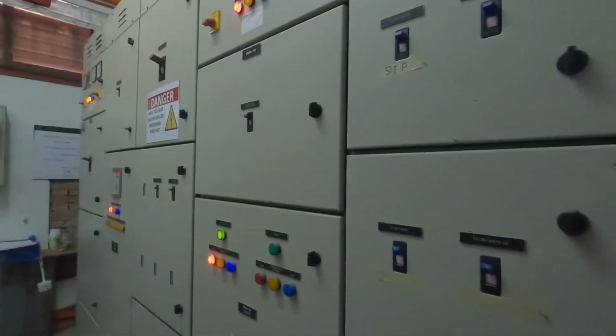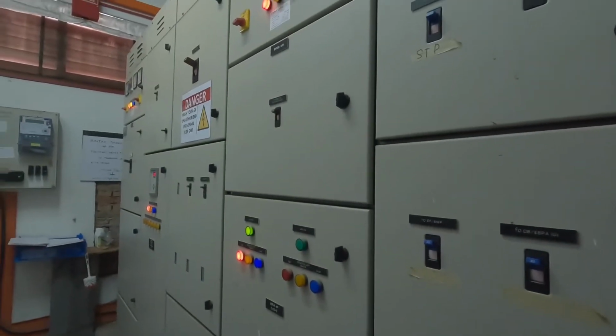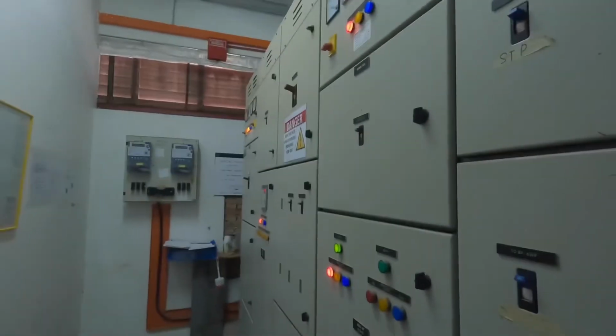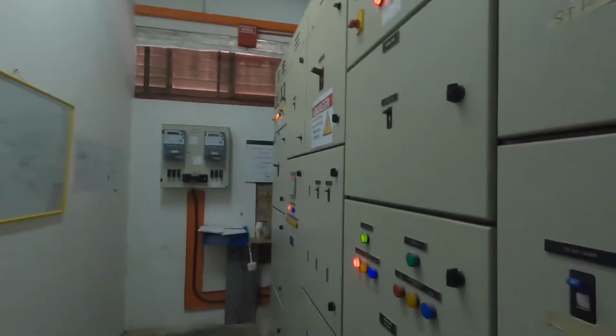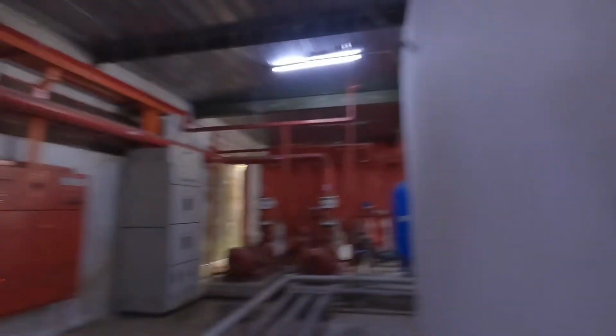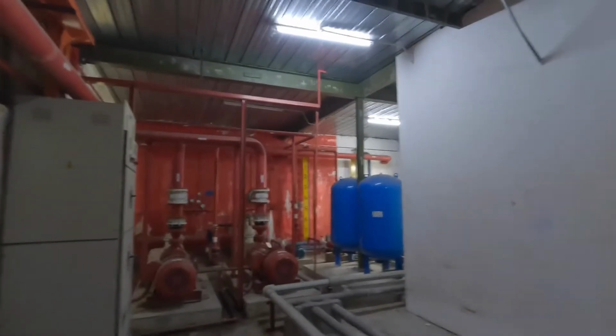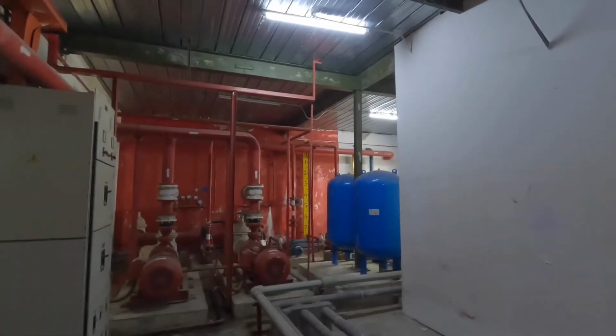Alright, okay, then there's one thing not available: CPR chart, first aid chart. In case there's any electrocution, we need to do CPR. That one is the regulation, so the CPR chart I have to put affixed to the wall, either here or anywhere else, so can be seen. Okay, so next door we have the fire pump room here. This is the fire pump room. Not much big issue, everything is quite old, but no problem here, so we just concentrate on the electrical room.